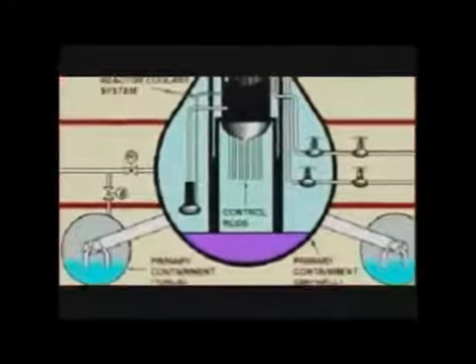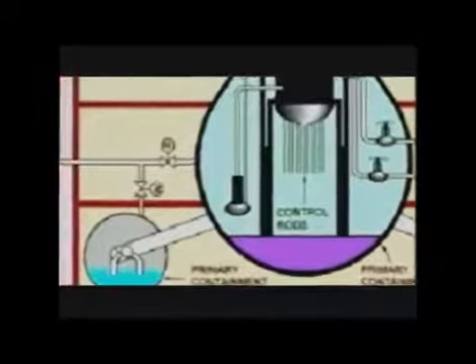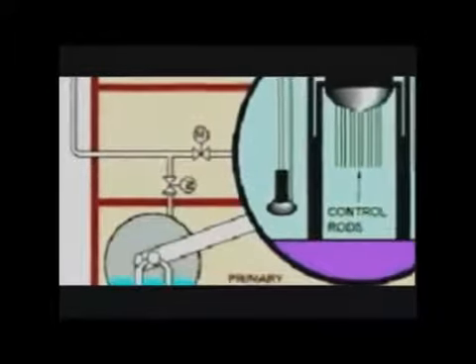This is a really important distinction. The nuclear industry, the Nuclear Regulatory Commission, and the Japanese are saying that we can make the vent stronger so that this accident can't happen. But if the nuclear head is lifting up, the vent is irrelevant. The containment on the Mark I design has a design flaw that the containment vent can't solve. Whether or not the nuclear reactor containment at Fukushima maintained its integrity is a critical question to the operating fleet of BWR reactors throughout the world.